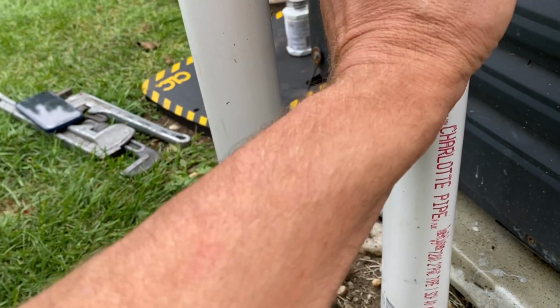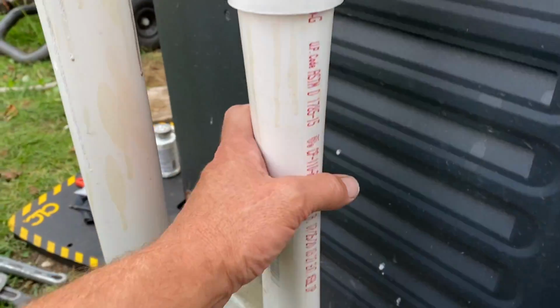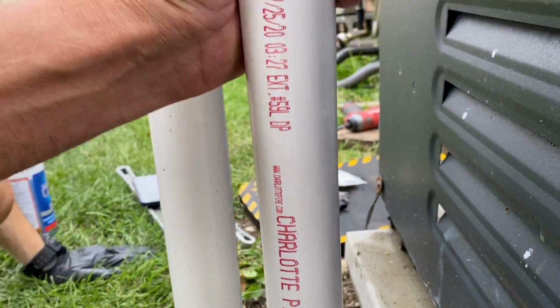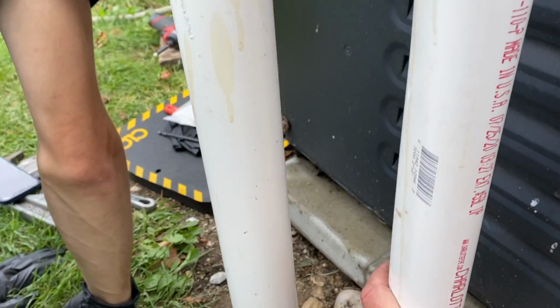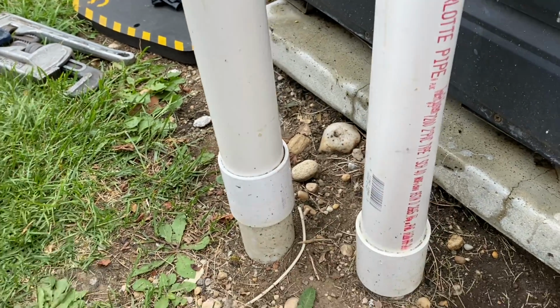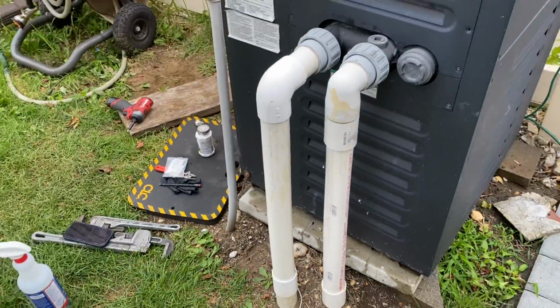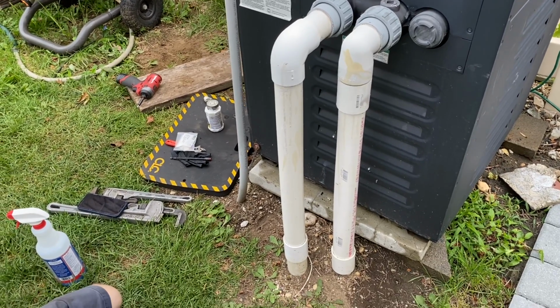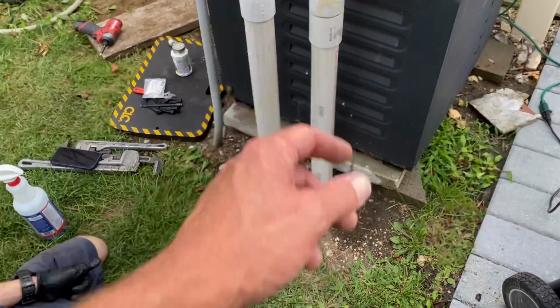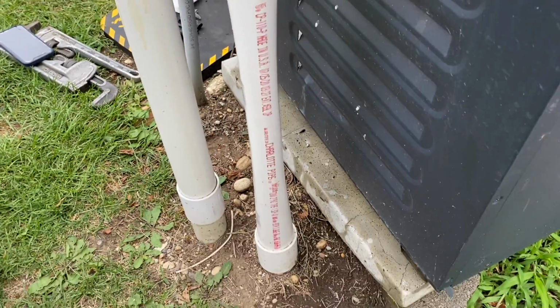Oh, was that because it was probably coming out of here since it wasn't going? No, I think maybe just flame. But it doesn't look charred or anything, but it is deformed. It lost its shape. So in replacing this, we're gonna have to dig a little bit to replace that. So there's up to the replacement cost. We have to excavate down there, expose the 2-inch, and then repipe. Wow, I didn't even notice that. Totally missed that. Look at that.